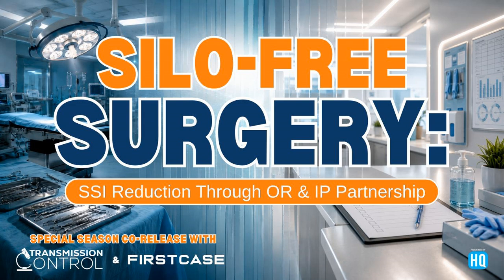Because you just said 6 log reduction, we will challenge the sites that are there. So there is a mitigation risk strategy that we go through in the test lab to see what we are doing. Are we over challenging? The first question is, are we over challenging the process? Right. And then that helps us decide, do we cut down the challenges? And if we do cut down the challenges, and even if they fail, it goes back to the manufacturer, like, okay, I don't think this is going to work. Right. So that makes sense. So you start with worst case scenario, and then you validate the process, and then you move it back towards feasibility given the established parameters. Yes. Keeping in mind that we still do worst case, but not to the extreme at this point. We go in the middle.